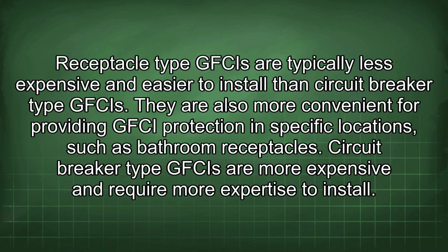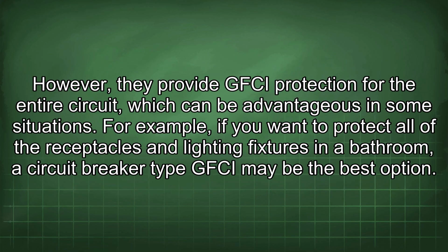Receptacle type GFCIs are typically less expensive and easier to install than circuit breaker type GFCIs. They are also more convenient for providing GFCI protection in specific locations, such as bathroom receptacles. Circuit breaker type GFCIs are more expensive and require more expertise to install. However, they provide GFCI protection for the entire circuit, which can be advantageous in some situations. For example, if you want to protect all of the receptacles and lighting fixtures in a bathroom, a circuit breaker type GFCI may be the best option.